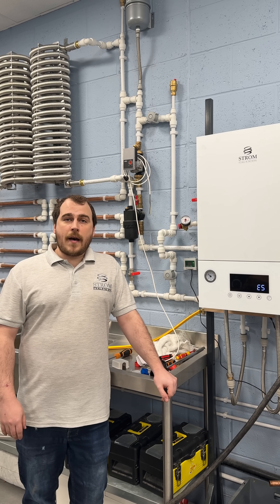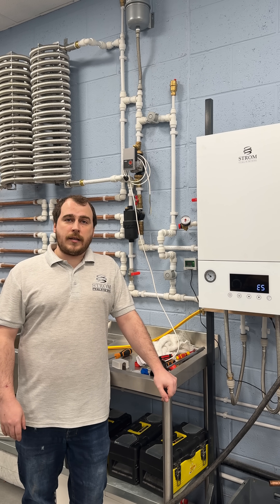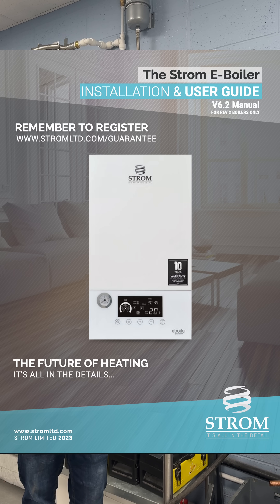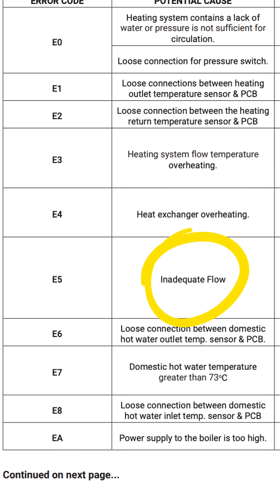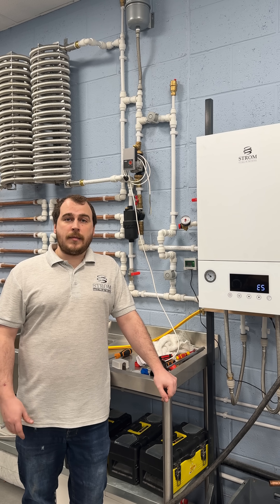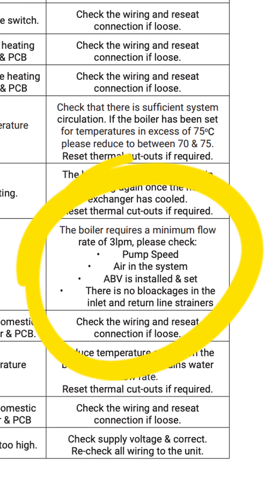The E5 error code will trigger when the boiler recognises that the system flow is below 3 litres per minute. Things that can contribute to this are things like air in the system, sediment, debris, and valves that are slightly shut.